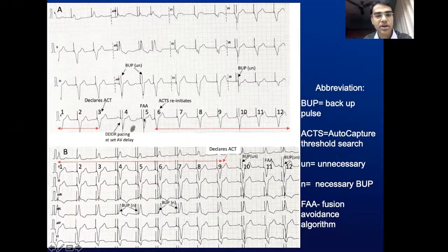The PR interval is longer here because another algorithm, which is an inherent part of the auto capture algorithm, comes into play, called the fusion avoidance algorithm. And that too, although it was an adequate capture, as we can see on the ECG, for the pacemaker there was no evoked or less evoked response, and it was again annotated as a loss of capture and a backup pulse came. So I annotated them as backup pulse, which is unnecessary because it was actually an inappropriate backup pulse which has come here. And because of this, the pacemaker again goes into auto capture threshold testing, and this starts the auto capture threshold search. The same or a similar thing happens in panel B.